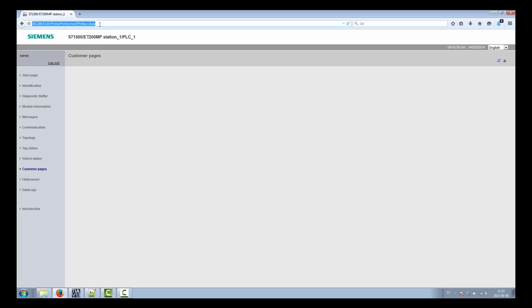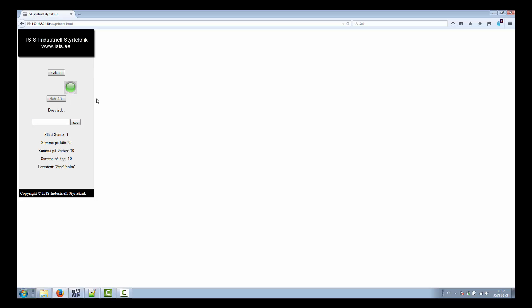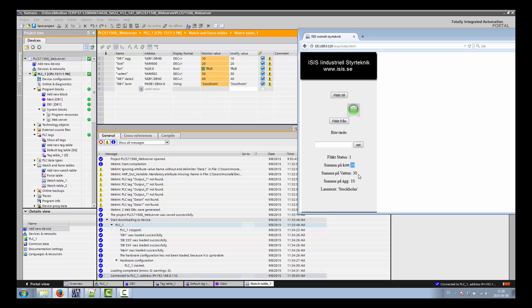After logging in, this is the page we designed. You can see 'fan status' showing the binary value — it's 1, which is correct. Kött is 20, matching our watch table. Vatten (water) is 30, which is correct. Egg is 10, matching our value. The alarm text from the data block also appears. Everything matches.